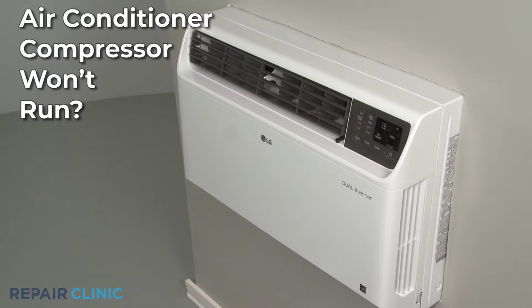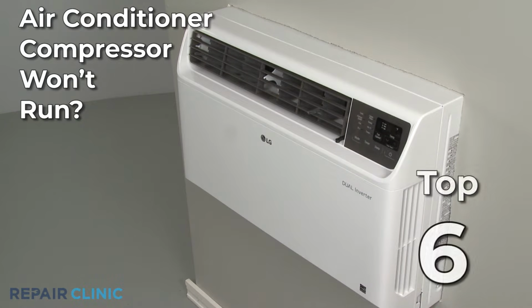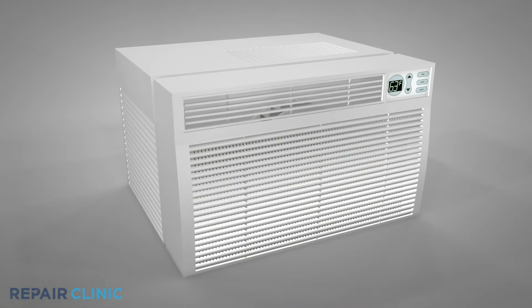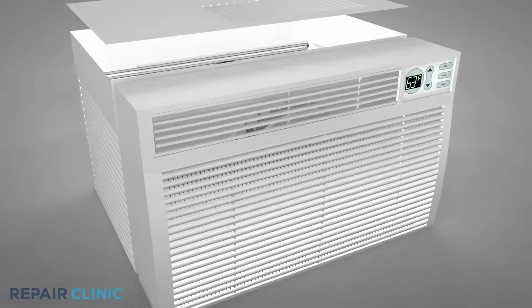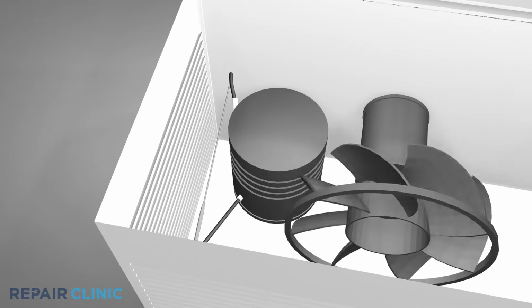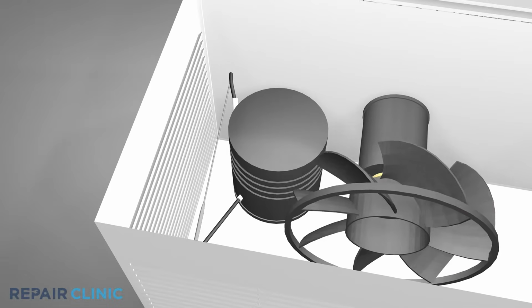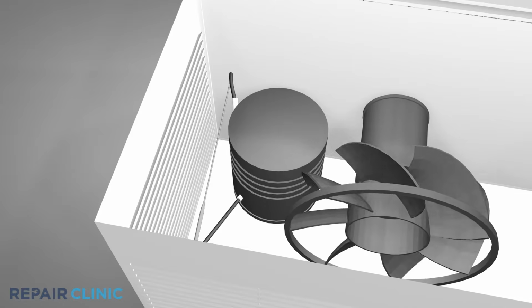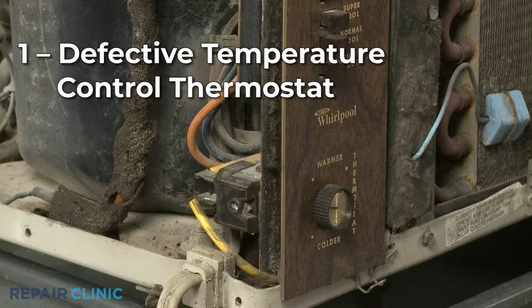If your air conditioner compressor won't run, here are the 6 most probable causes. When the air temperature rises above a set point, some models have a temperature-controlled thermostat that will switch on the power to both the fan motor and the compressor. A defective thermostat can prevent voltage from being sent to one or both of these components.